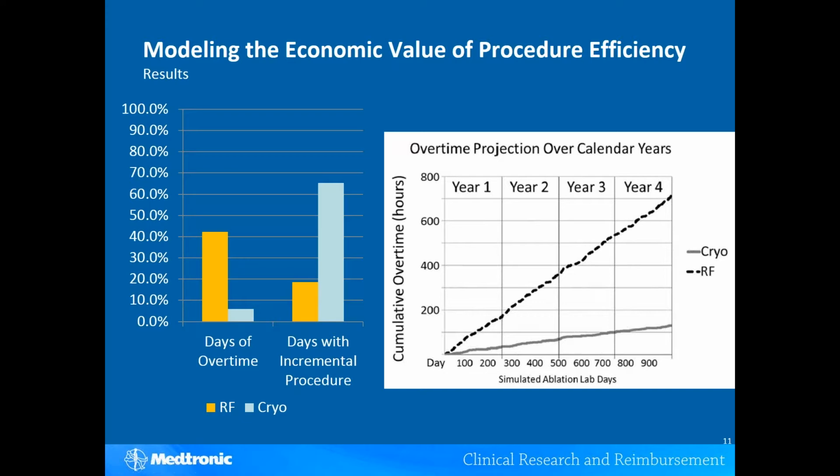This sort of presentation we use a lot at hospitals where the physicians already desire to use cryoballoon technology, but they've run into a barrier at their administration level in investing in it. When they need to do these ablation cases, there's a capital outlay at the beginning. There's a generator, as it's called, a fairly big, substantial piece of equipment that sits in the EP lab and generates the energy that allows the ablation to happen. And that's a 6-figure investment for the hospital.